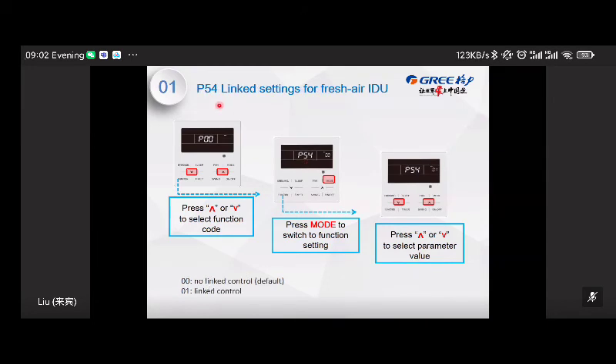Next one, P54. That's the linkage control for fresh air. For example, in your project, there are ordinary indoor units and fresh air indoor units, right? You can just use one controller to control them simultaneously. However, the default setting is no linkage control. You can just change to linkage control. So if you set this one, the controller will control the ordinary indoor units and the fresh air at the same time, right? Just to make them run synchronously.